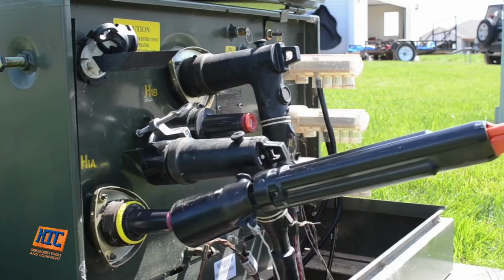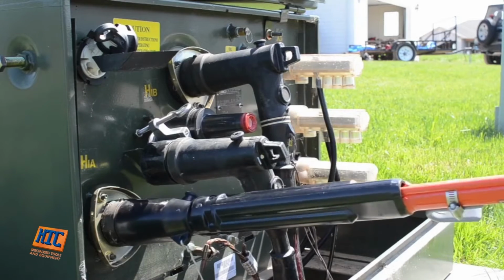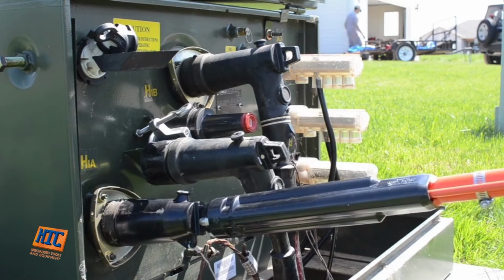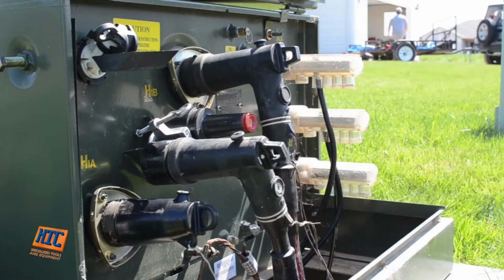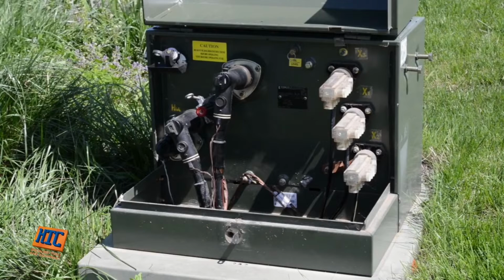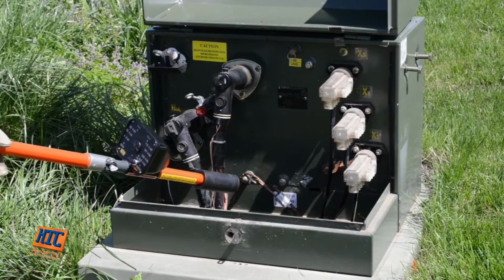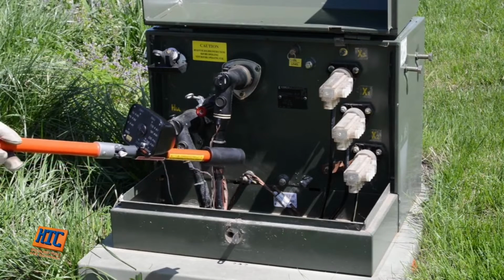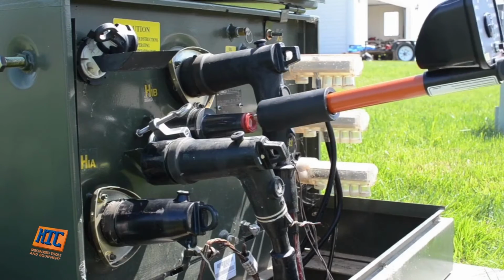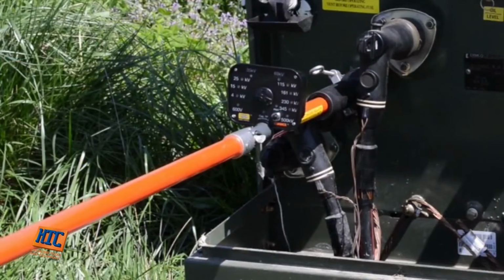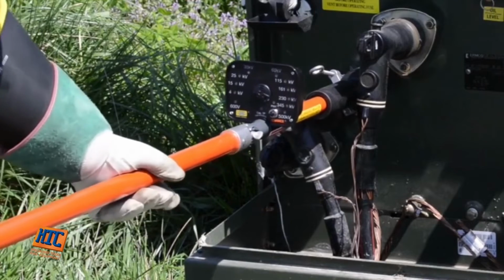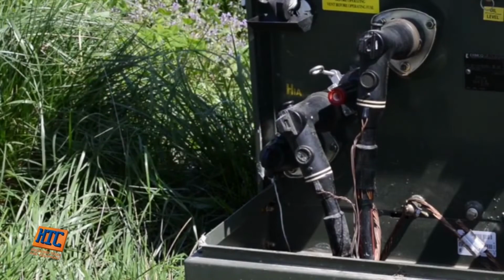The RV can also check for potential on an underground cable between transformers or switchgear. Here, notice that a 200 amp load break elbow already has been pulled and parked on a feed-through bushing, and the primary bushing has been covered, all with hot sticks. For this use, the RV has been fitted with a bushing adapter on the front. Simply insert the probe of the adapter into the feed-through bushing. Notice that only the power LED is blinking and none for any voltage class, indicating that there is no voltage present, that the circuit has been de-energized.